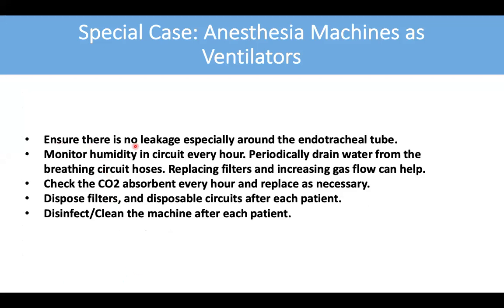Please remember to ensure that there is no leakage, especially around the endotracheal tube. You want to monitor the humidity in the circuit every hour, periodically draining water from the breathing circuit hoses and replacing filters as necessary. If there's a lot of humidity in your circuit, you can dry the circuit by replacing the filters and increasing the gas flow. Please note that you do not want to do this for really long times, as that can dry a patient's airway. You want to check the CO2 absorbent every hour and replace as necessary.